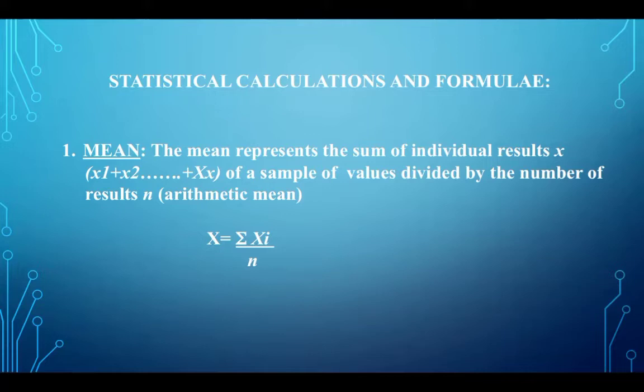What is the importance of mean for us? Mean tells us about accuracy. What is accuracy? How close our result is to the true value. How is mean telling us? Suppose the manufacturer mean is 100 for glucose and your monthly mean is 90 or 110, it is significantly away from the manufacturer mean.